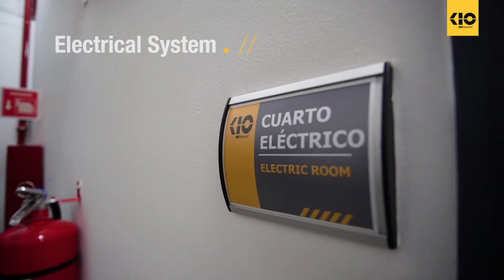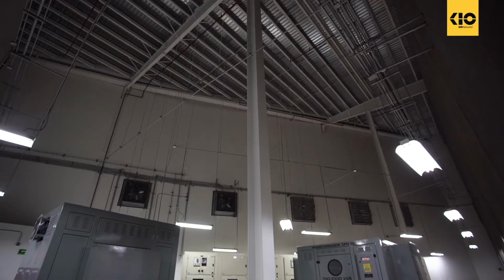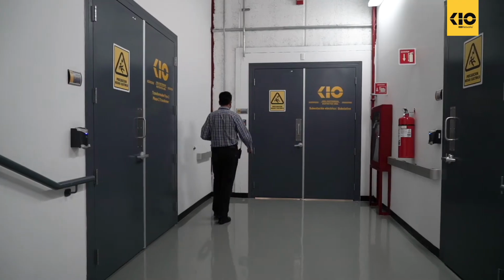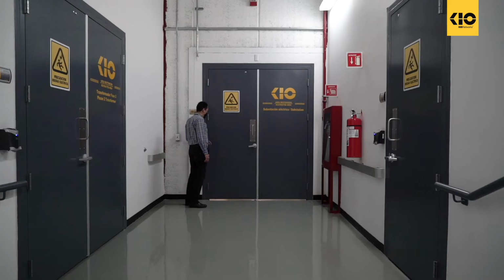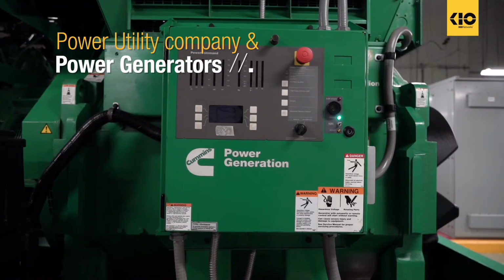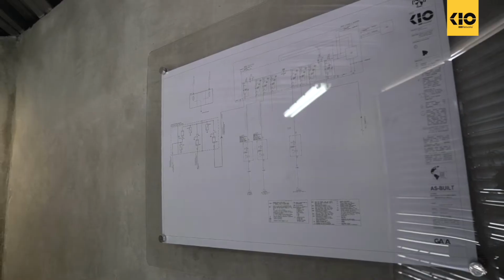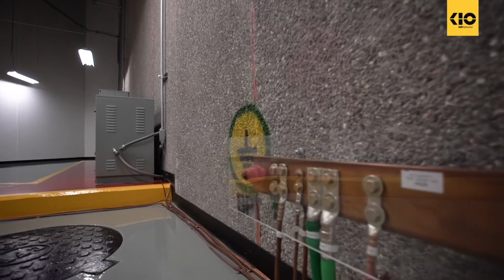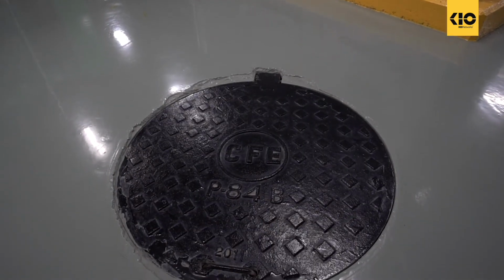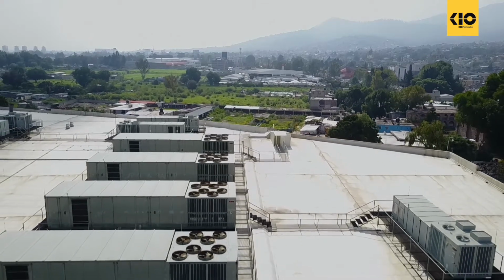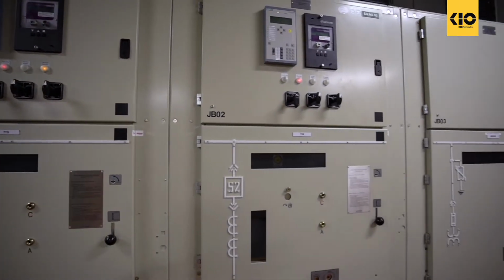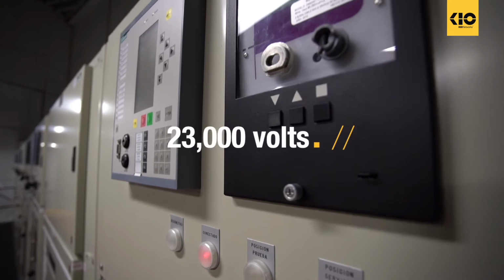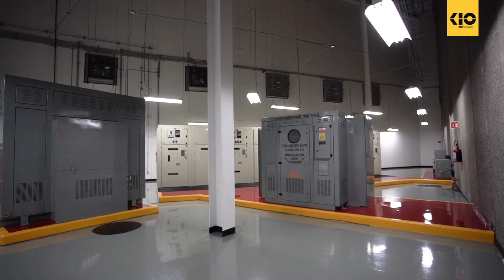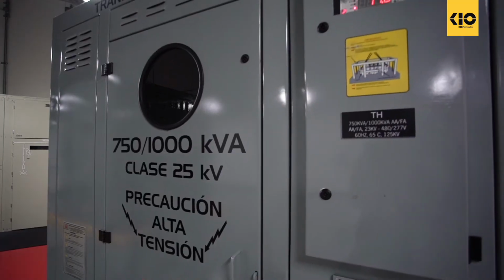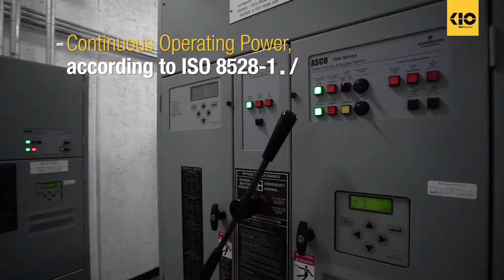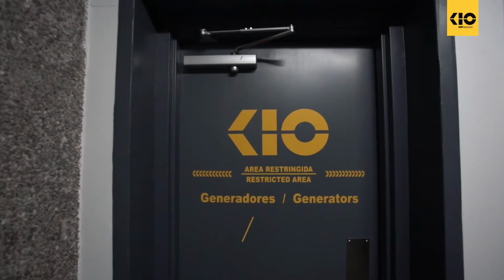The redundant electrical system is one of the most critical elements to maintain the continuous operation of our data centers. KIO MEX5 has two different sources of electrical energy: the main utility and the power generators within the facilities. The utility includes greater reliability with double power supply by different routes, a dedicated underground primary supply, and an overhead secondary supply. The connection receives medium voltage from the utility power network at 23,000 volts, reducing the voltage to 480 through two redundant substations with their transformers. In the event of a utility power outage, we have a transfer system to obtain the supply from our 6 generators.